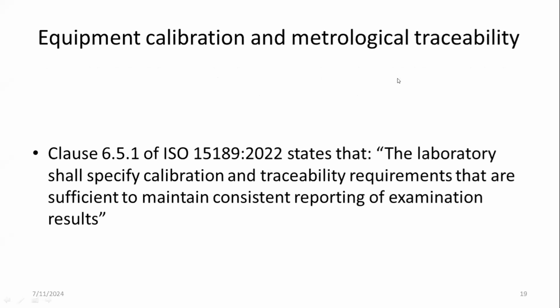So, equipment calibration and metrological traceability. This is picked from 15189, in the resource requirements of 6.5, that states a laboratory shall specify calibration and traceability requirements sufficient to maintain consistent reporting of the examination results. So this means that as a requirement, we, as the labs, are supposed to ensure that we maintain the traceability of the measurements. And this traceability is picked from the equipment calibrations that we do. So as equipment users, we are supposed to be able to identify who is going to provide the traceability.